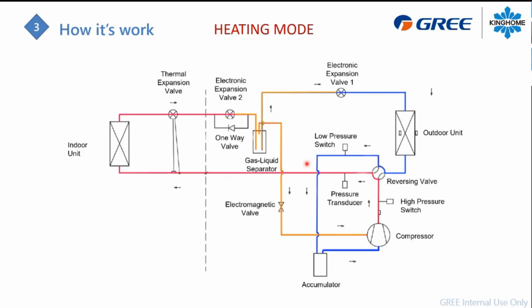If we are going in heating mode, the small difference between those two is that you start the cycle with the discharge high temperature, high pressure refrigerant, then your reversing valve is activated. Because it's activated, the valve here will change the refrigerant flow. So you will take your high pressure and push it into your indoor unit directly. Then the air will cool down the high temperature here. You will have a kind of flashing refrigerant, so high pressure liquid, high pressure vapor. You will hit the bypass here in the TXV, and then going back to the outdoor unit, you will hit the electronic expansion valve number 2.